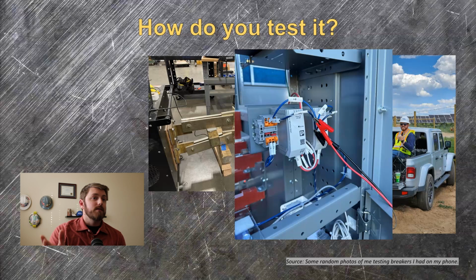The process is very similar to draw breakers that you're going to test on a bench outside the gear. When you've got it stabbed up to your primary injection test set, use a small 24-volt power supply connected straight to the maintenance mode inputs on the breaker to enable it for testing. You'll need to determine what your benchmark is that the maintenance mode is actually on. Whether it's a little blue LED or it's a setting buried in the menu somewhere, note that as your report.